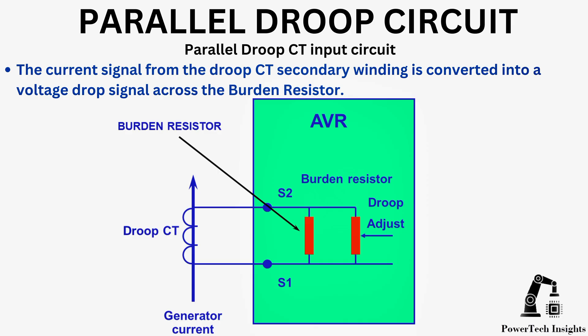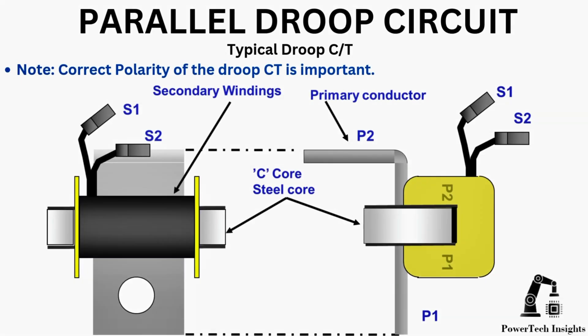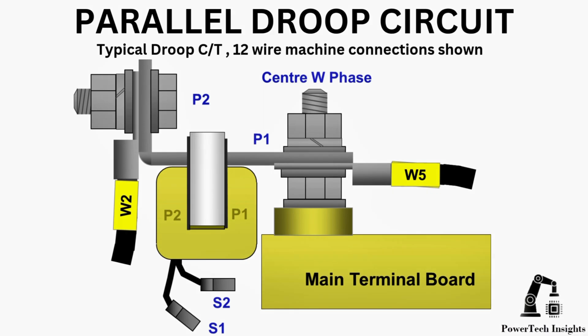Parallel droop CT input circuit. The current signal from the droop CT secondary winding is converted into a voltage drop signal across the burden resistor. Note: correct polarity of the droop CT is important. Typical droop CT 12-wire machine connections are shown in this picture.